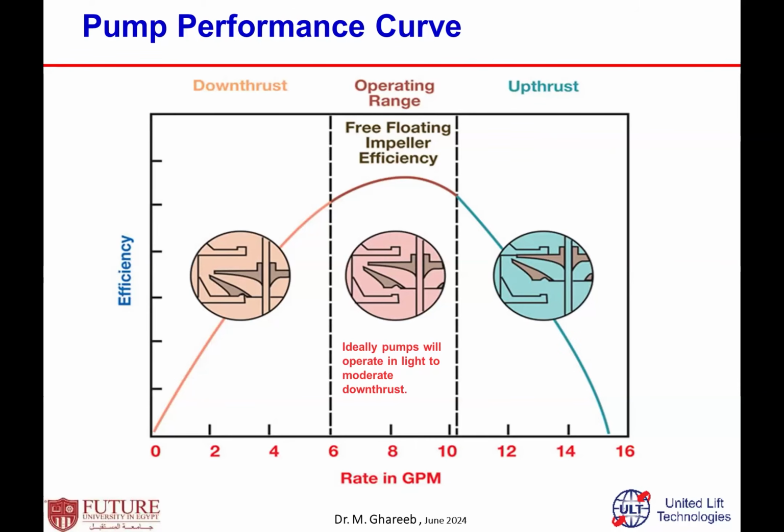Within the recommended operating range, the impellers and diffuser are in a free floating impeller condition, not contacting the top or the bottom. In your design, you have to run within this operating range in order to have more running life.